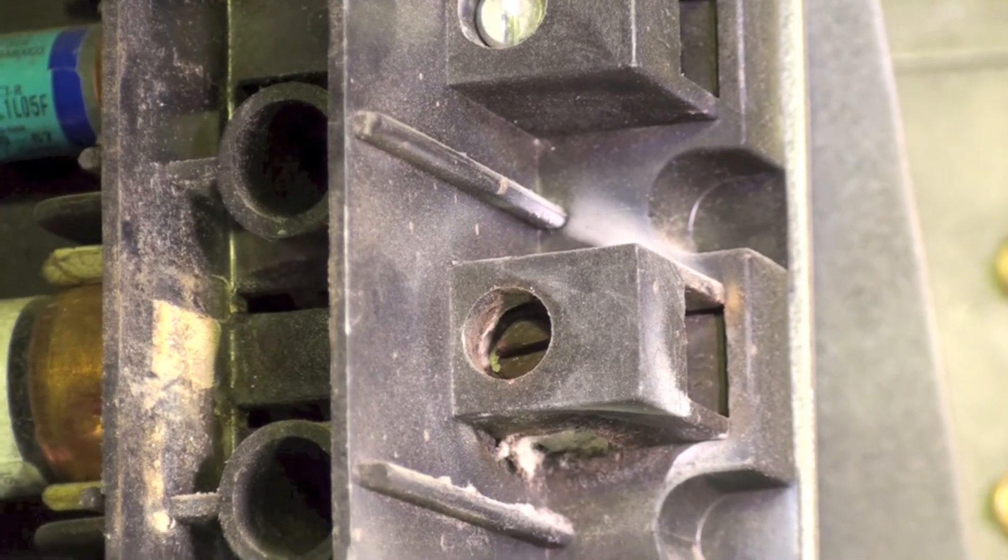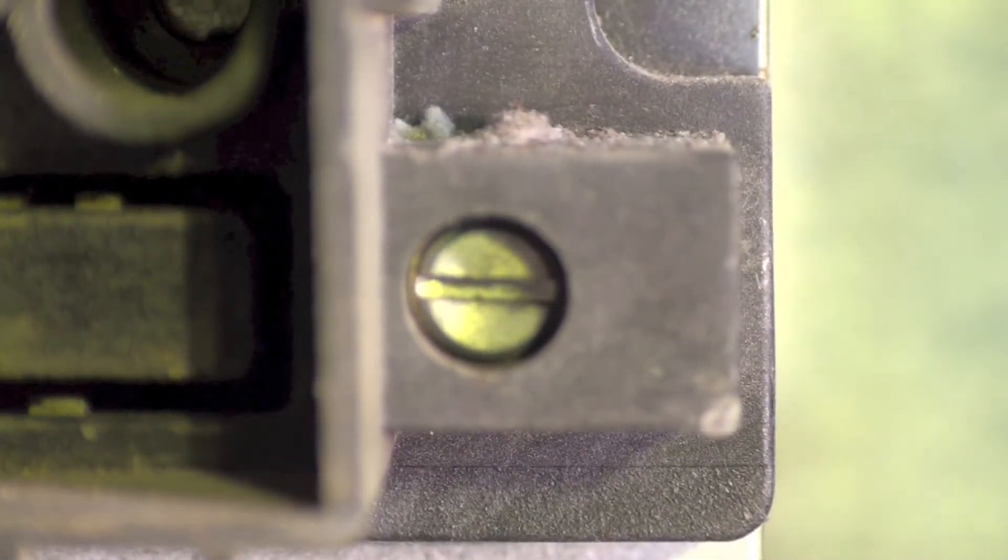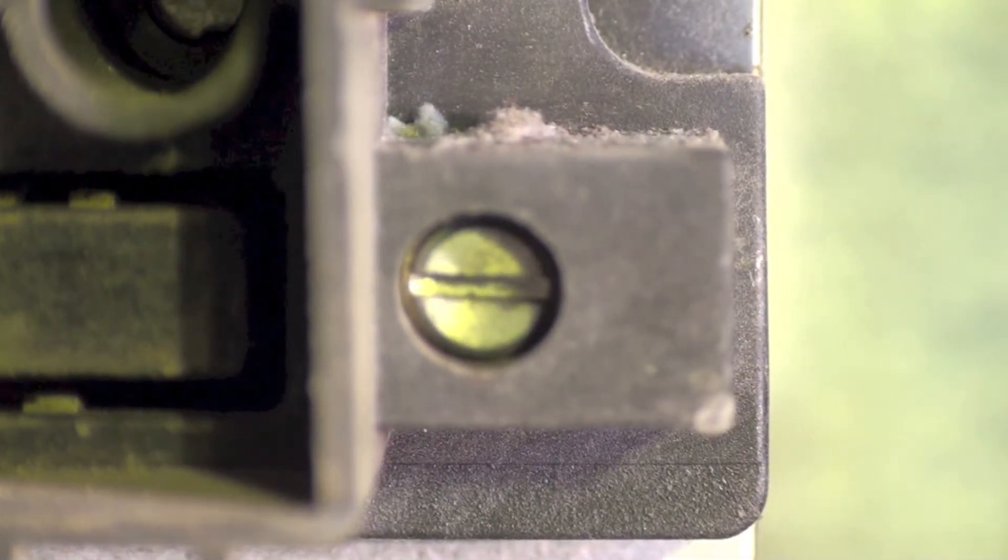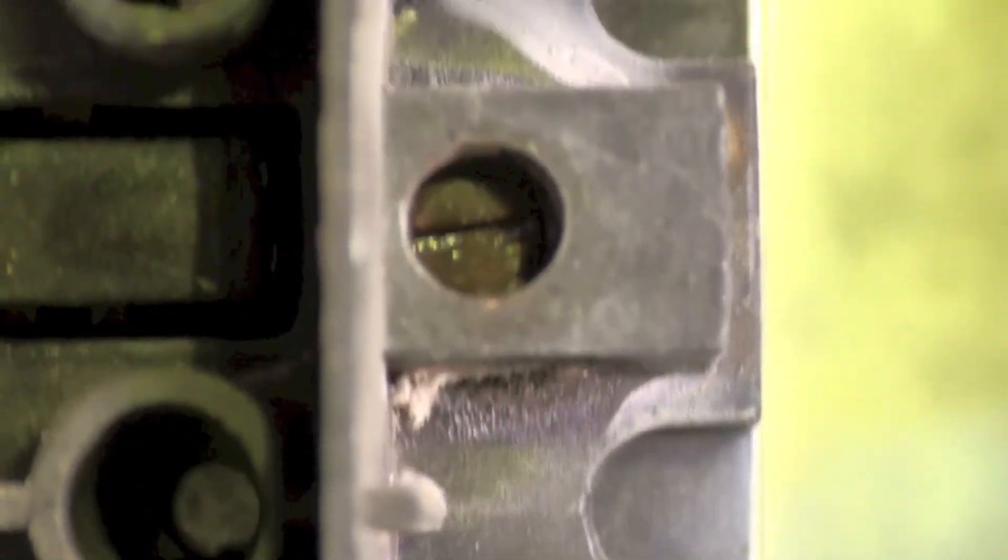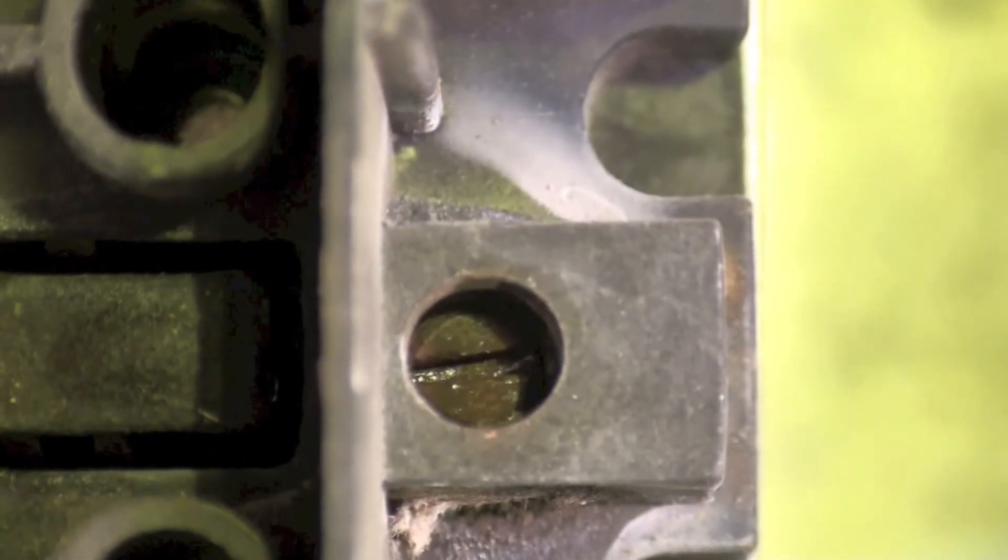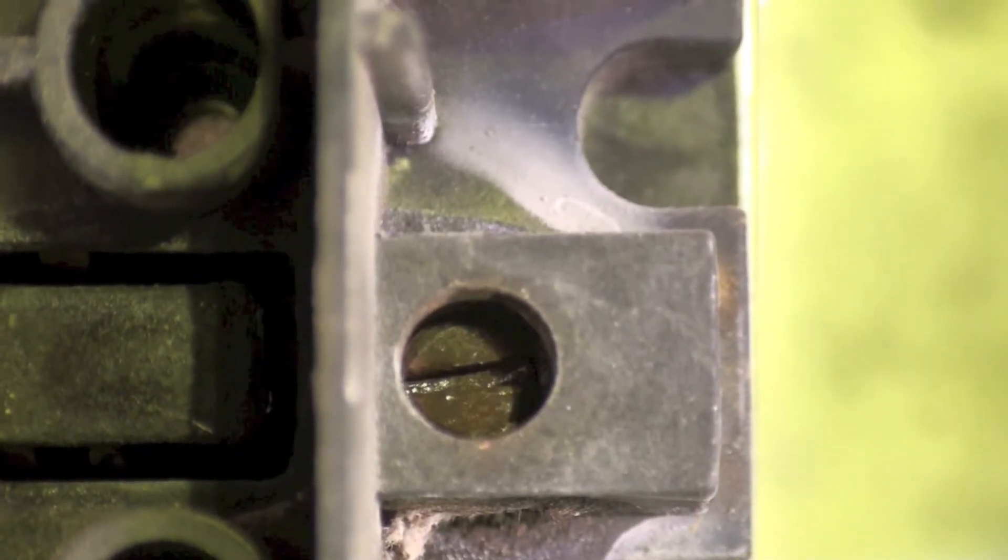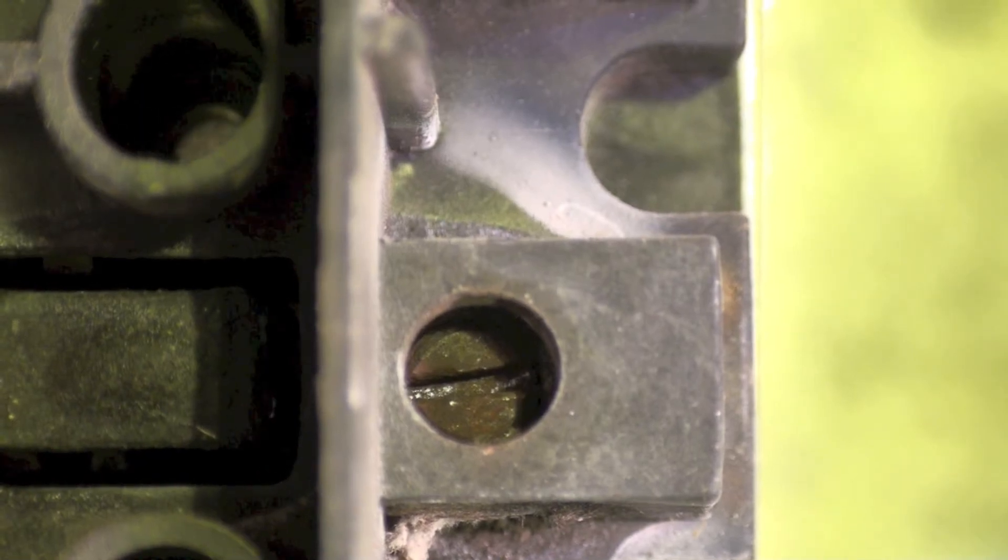There's the bottom screw and you can see it looks pretty good. Now look at that screw in the second one up - it's discolored. When I try to turn it, it's turning but you can hear it crunching with stuff falling out of there.